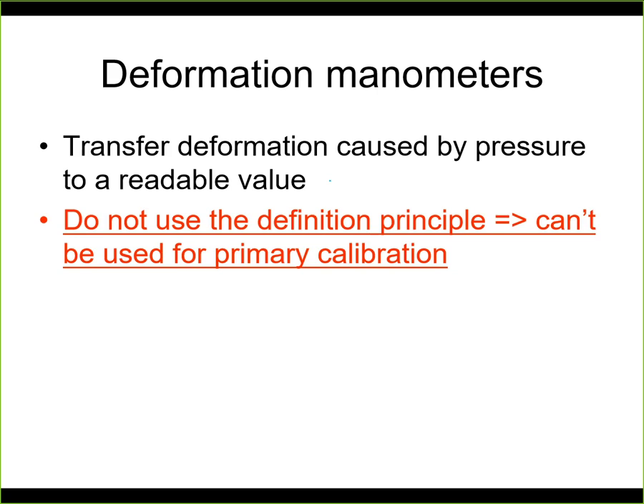of pressure gauges. First of all, we need to know that we will transfer the pressure that we measure to a deformation of some element. So this is not directly the definition of pressure, and we cannot use this for primary calibration to calibrate all the other instruments. But anyway, the accuracy of these deformation manometers may be quite high as well.